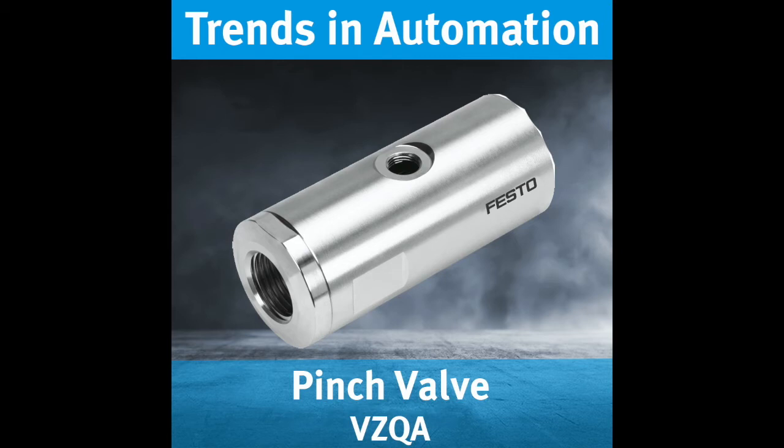The second is what most process industry folks will think of when they hear the phrase industrial pinch valve. Like our VZQA, these are also designed for direct media contact, but they come in much larger sizes, like 2 inches and up, as opposed to our pinch valve with sizes ranging from 1/4 inch to 1 inch. Because of their size, these large pinch valves require the addition of a linear actuator in order to automate them. The actuating mechanism for our VZQA pinch valve is already integrated into its housing, so there's no need for additional accessories other than a pneumatic fitting so it can get some air.